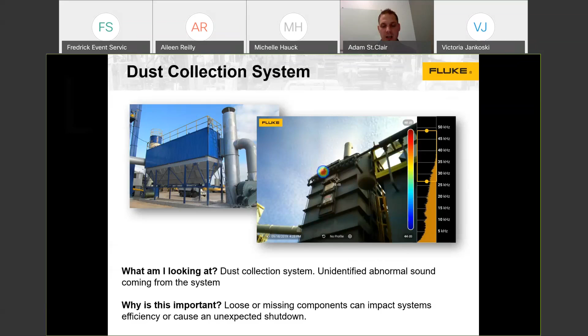It's a neat example—it has nothing to do with energy savings or cost savings, unless you think about what would happen if the dust collection system shut down because critical components rattled off or shook free. They were impressed that acoustic imaging isn't about air, gas, or vacuum specifically—it visualizes sound. So anytime sound can help solve or identify a problem, acoustic imaging can really be a benefit.